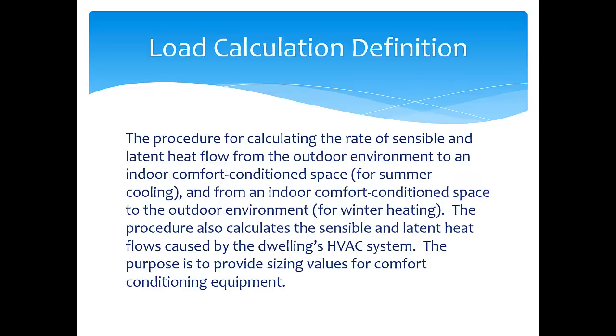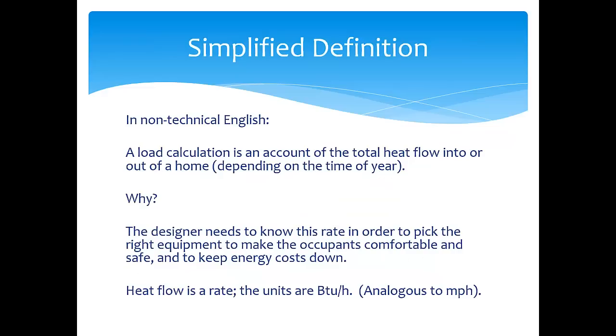So what is a load calculation? It is the procedure for calculating the rate of sensible and latent heat flow from the outdoor environment to an indoor comfort condition space for summer cooling, and from the indoor comfort condition space to the outdoor environment for winter heating. The process also calculates the sensible and latent heat flows caused by the dwelling HVAC system. The purpose is to provide sizing values for comfort conditioning equipment. In simpler terms, a load calculation is an account of the total heat flow into or out of our home depending on the time of the year, so that the designer knows the rate of heat flow. Note that heat flow is a rate and has a unit of BTUH, which stands for British Thermal Units Per Hour.